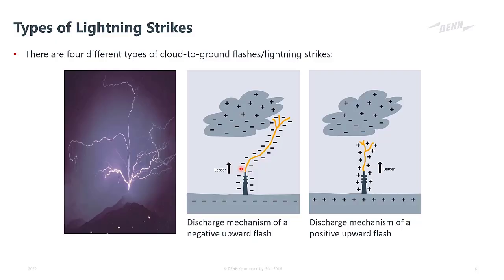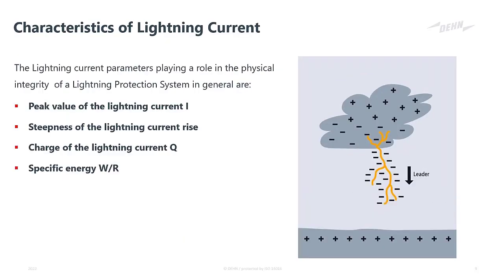And this is typically what would cause harm to personnel inside tall structures, or would cause damage to tall structures and equipment within those structures, like a turbine blade. On the left, you can see a picture of what that typically looks like. You can see all the concentration of charge at one point as it goes up into the clouds. Now, a lightning strike has four main characteristics that we consider. These four characteristics form an essential part of lightning protection design, equipment, lightning protection components, how they are tested, and each of them plays its fair role in why the standards are written the way that they are.